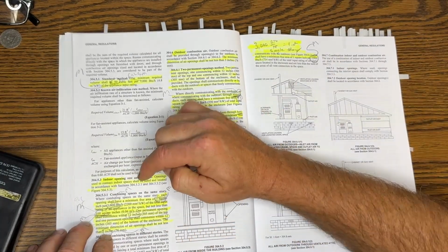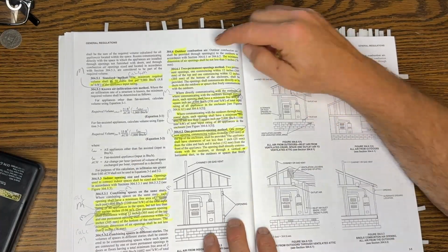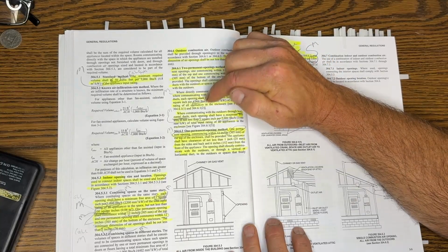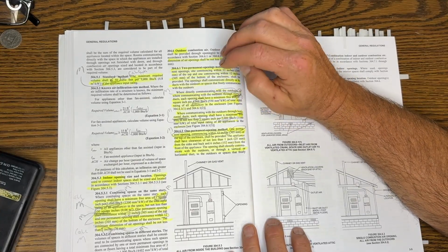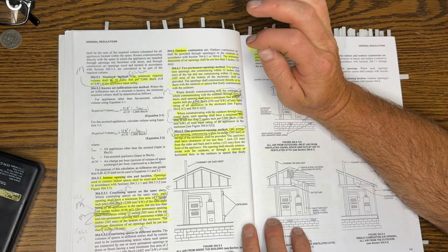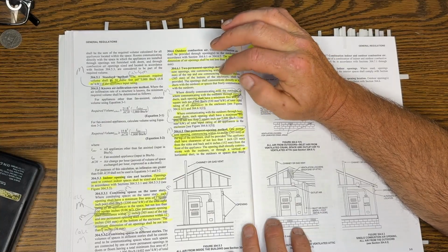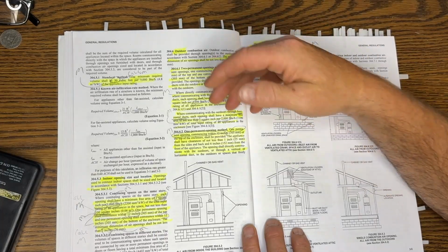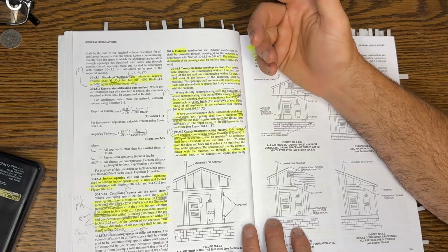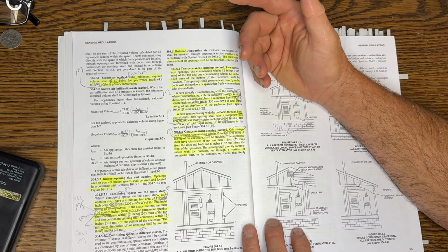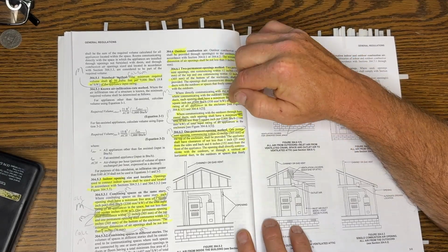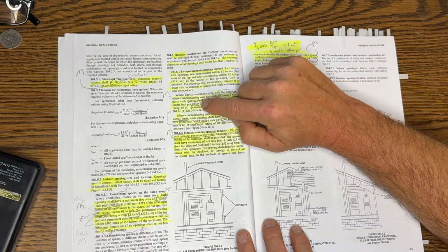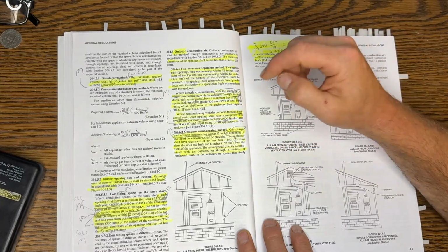So this is inside opening size, and then you have the outdoor combustion air. This is the piece that always gets you. It's 1 square inch per 4,000 BTU, and you've got to double that. The question was very clear: what's the overall square footage for an outdoor opening? Let's say they give you 200,000 BTU. 4,000 divided into 200,000 is 50 square inches, but the actual number would be 100 square inches, because that has to be doubled. It's 1 square inch per 4,000 BTU per opening, okay?